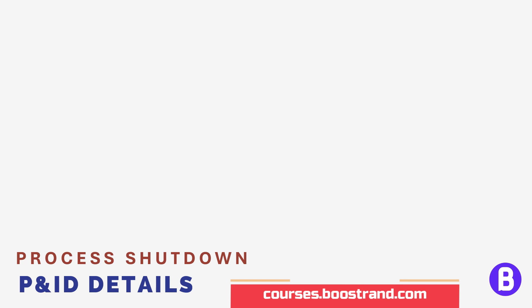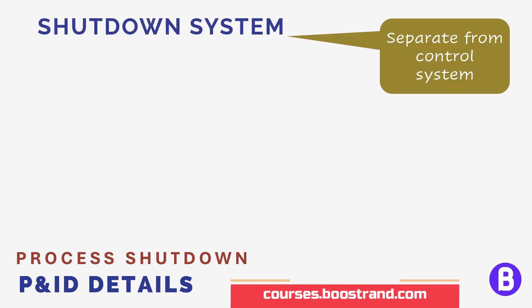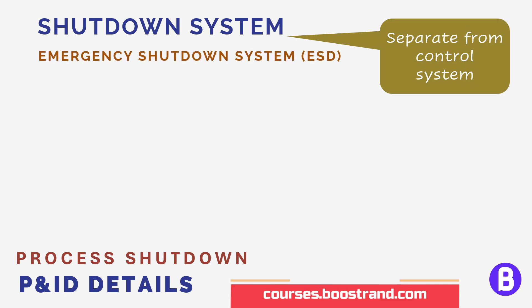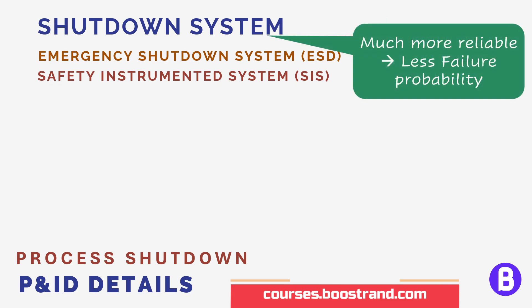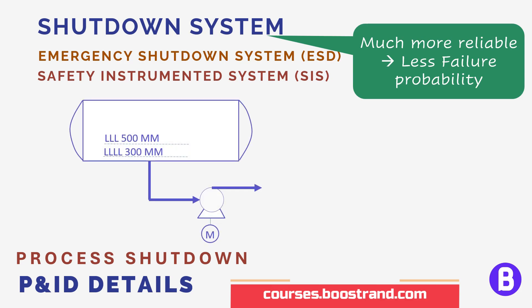In addition to the control logic, the P&ID also shows the shutdown logic. Usually, shutdown logic is executed by a shutdown system which is separate from the DCS. It's called the ESD system, which stands for emergency shutdown, or it can also be called SIS — safety instrumented system. The shutdown system should have higher reliability than the DCS, as we are talking here about safety and protection of personnel and equipment, not just normal operation. For example, if we want to protect the pump from cavitation, a signal from the level instrument is sent through a hardwire to the shutdown system.